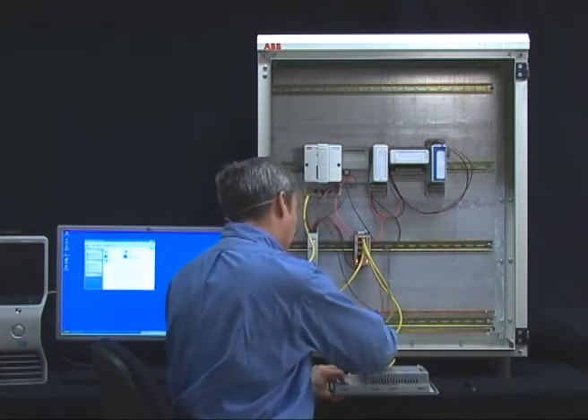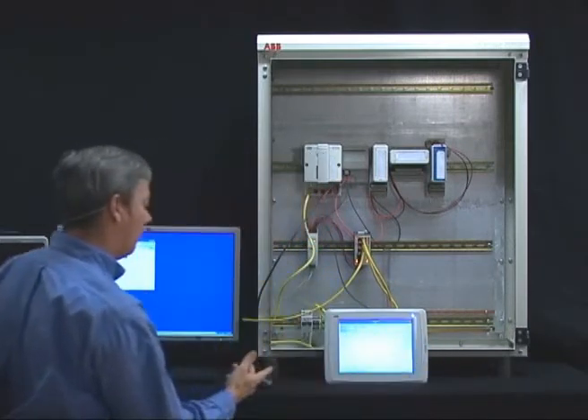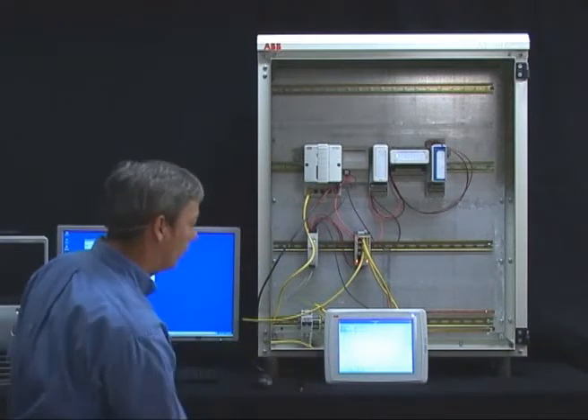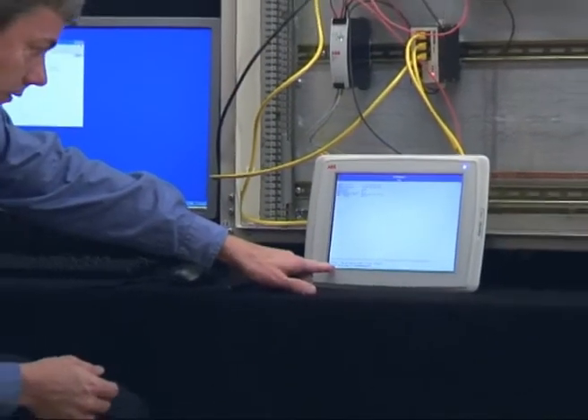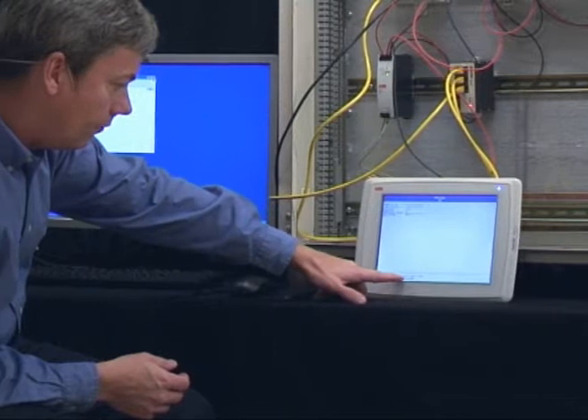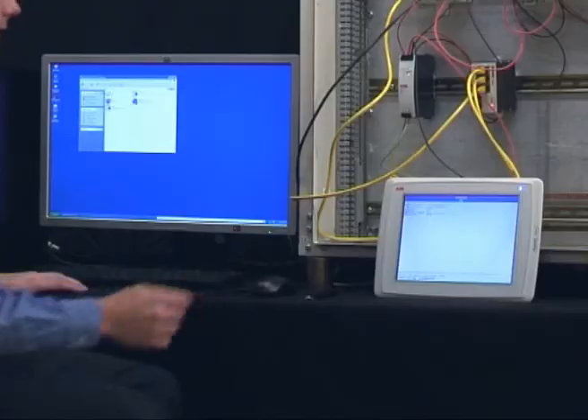We have to disconnect the power and connect the power, and then the panel automatically boots in a mode that makes it possible to download firmware. You can see here that the status says DIP switch OFF, ON, OFF, and that's what it should be. So if you have that, you have made the panel ready for downloading firmware.